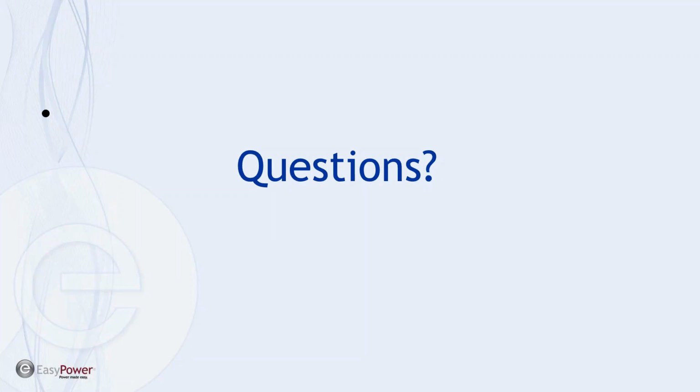Okay. Next question says, is there some standard to do a battery risk assessment? Ooh, well, guess what? 70E and Z462, they are the standards, right? So they have existing content in Chapter 3 and then Clause 6. And now what's happening is this flow chart that I'm alluding to, right? It's going to be added. I think it's going to be a no-brainer that it'll get approved.